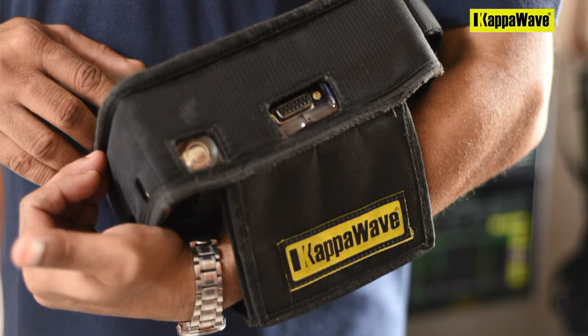Just touch and slide along the baseline to change the range or select from a saved list. Touch and slide on the vertical scale to change amplitude. Touchscreen is very sensitive and resistant to oil and grease used in UT. You may also use the range button to enter a value. You may use a stylus or your finger to work on display. Gauge can be easily moved anywhere and amplitude can be changed easily.